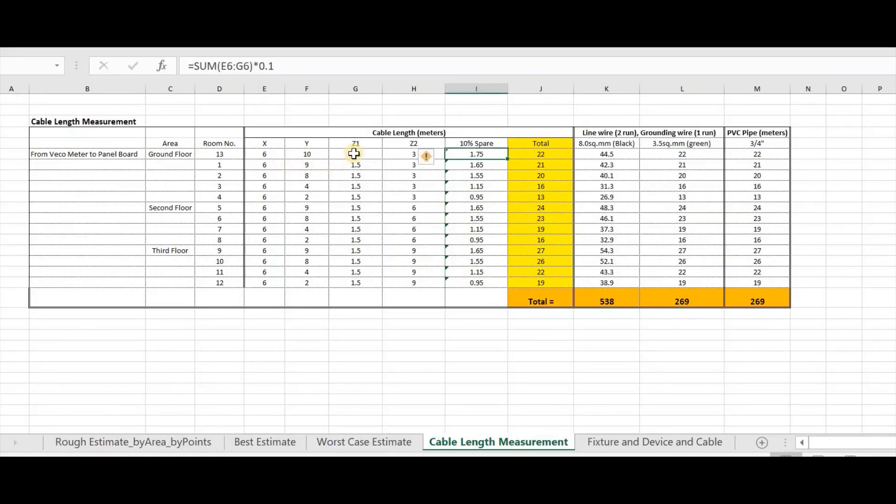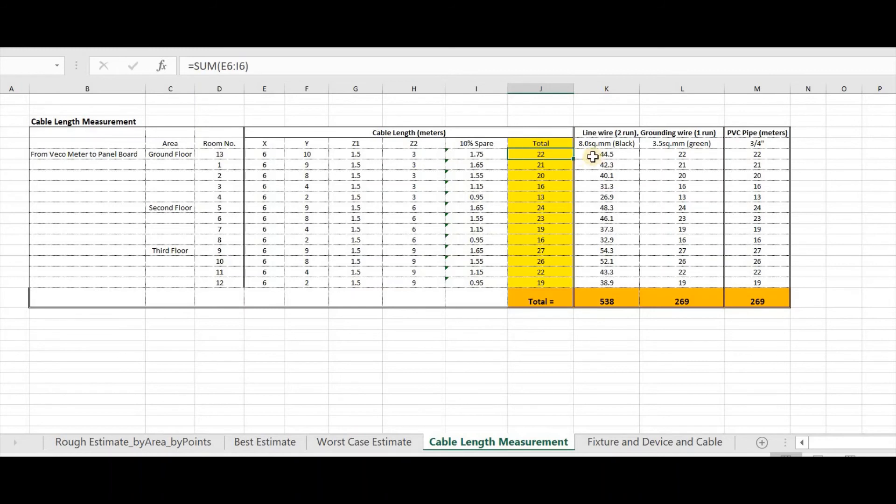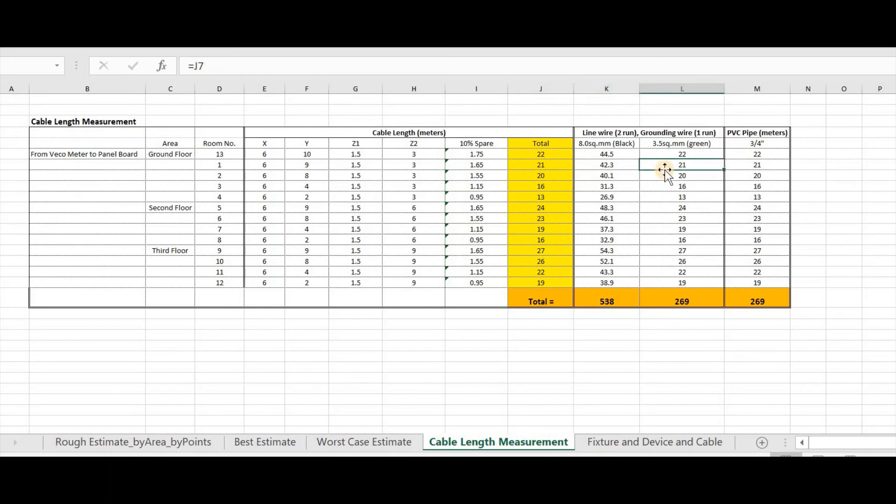We have Z1 from Veco Meter to ground and then Z2 from ground to each panel board. In this example, our Z1 is 1.5 meters, then our Z2 is 3 meters. Then I added 10% spare. This is for the snake factor. After that, you can have a total.